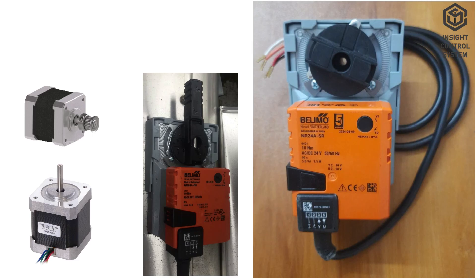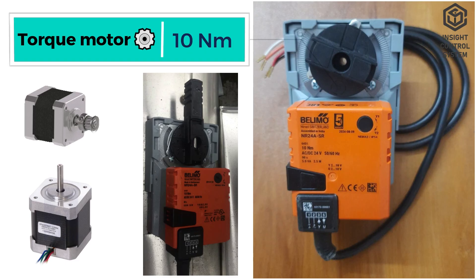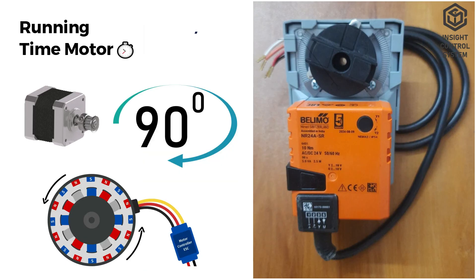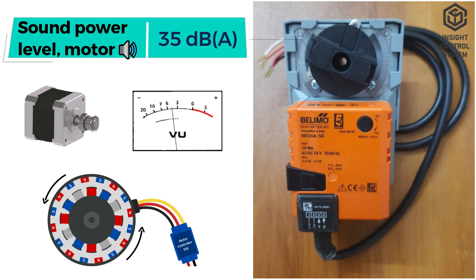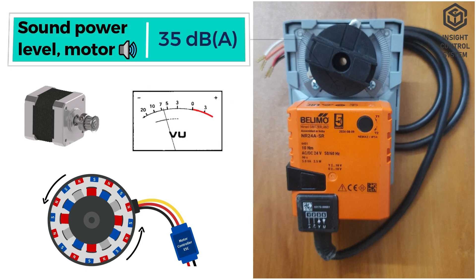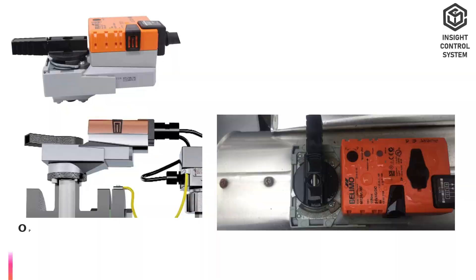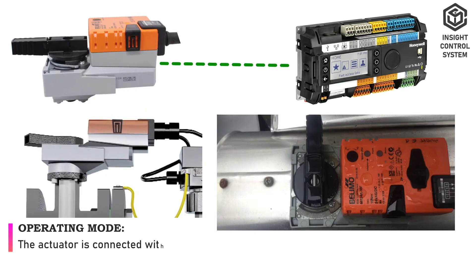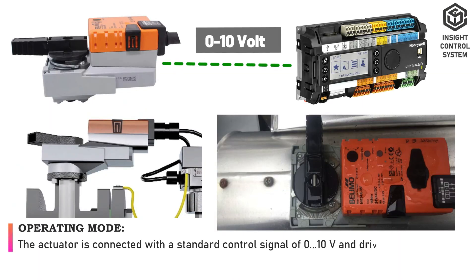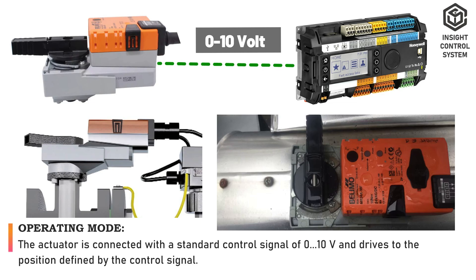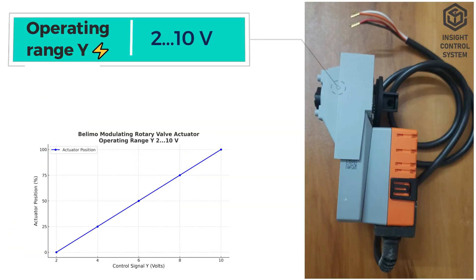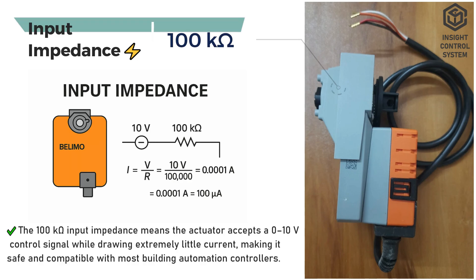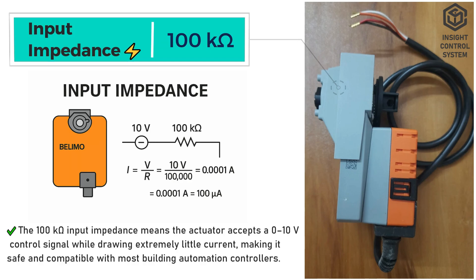Functional data: torque of motor is 10 Nm. Running time of motor is 90 seconds at 90 degrees. Sound power level of motor is 35 dB. The actuator is connected with a standard control signal of 0 to 10V and drives to the position defined by the control signal. Operating range is 2 to 10V. Input impedance is 100 kΩ.